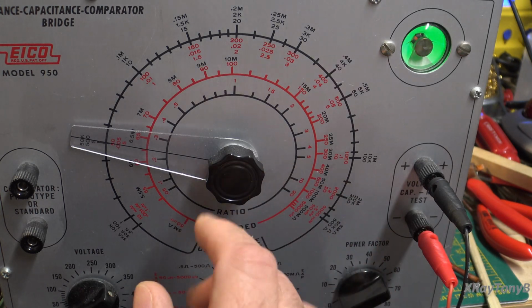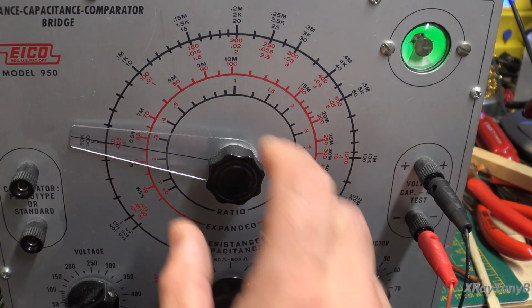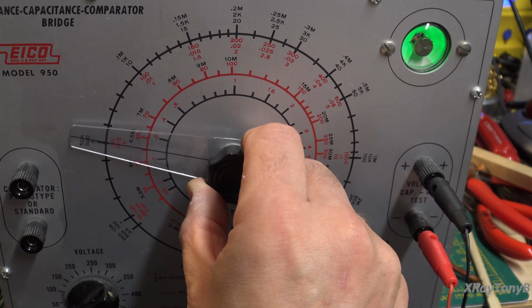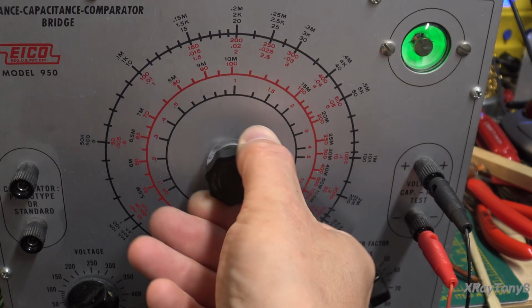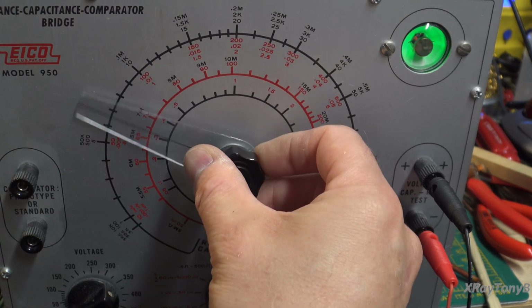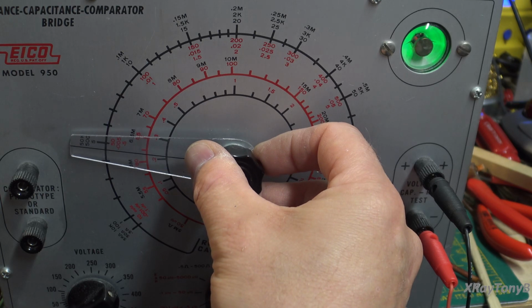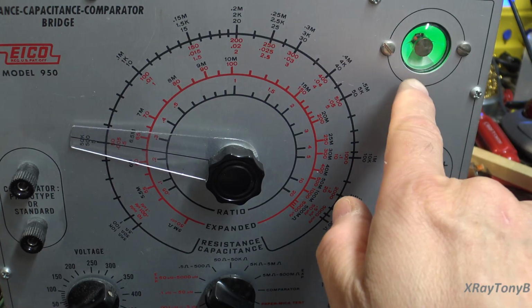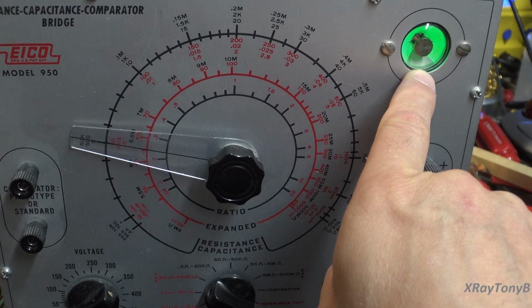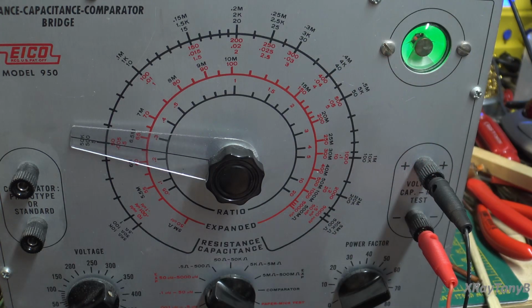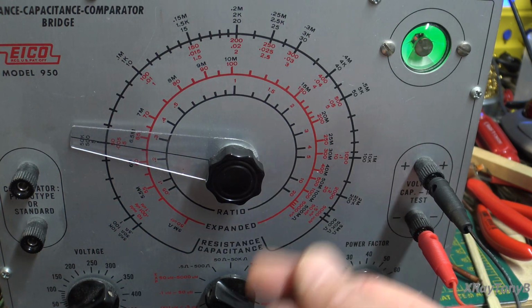So if we look here, it's reading low, and you can see it's only reading about 50 picofarads. So remember, if this closes and stays closed, that means it's shorting out. And down here is the amount of voltage we're applying to test it.